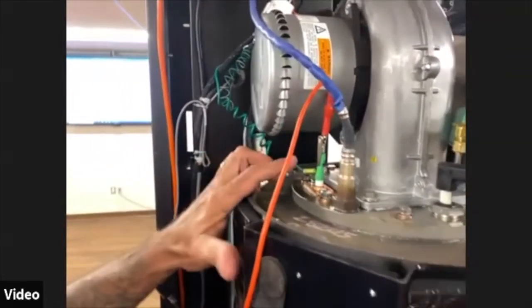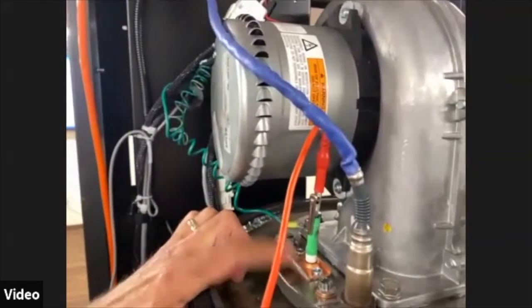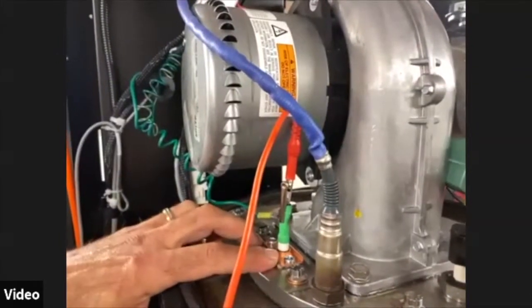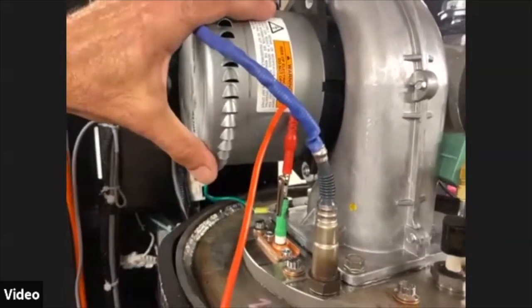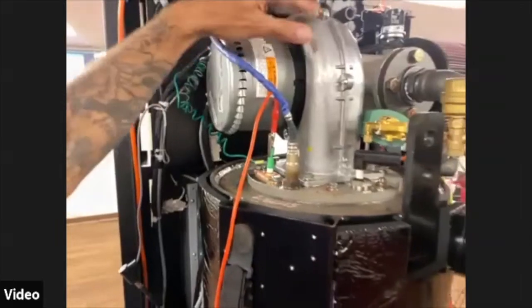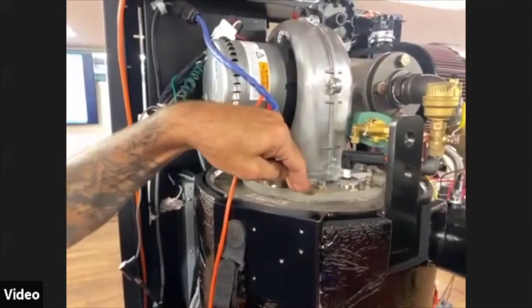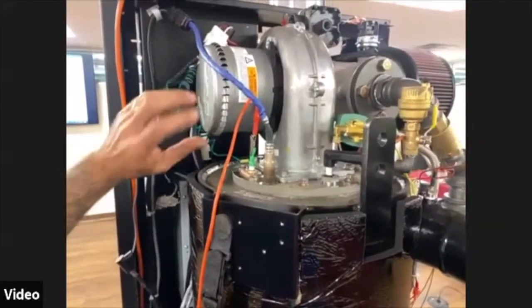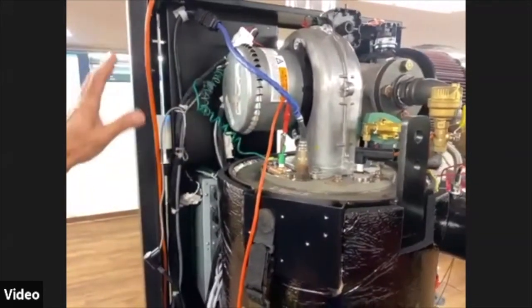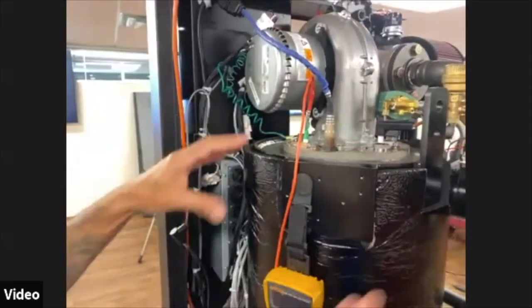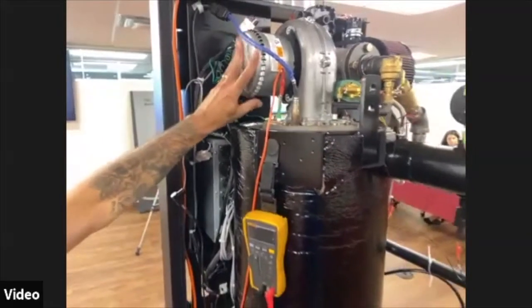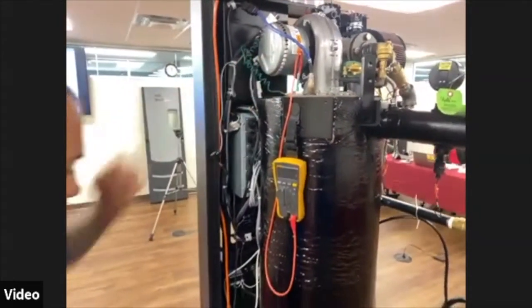And then our flame sensor would be here. 2 wires or 2 screws to pull that out. And this is our blower motor. On this particular model, the blower is mounted directly to the burner plate. You get to some of the larger models, this will be off of the top of the heat exchanger, and there's actually an intake elbow connecting the blower to the top of the burner.